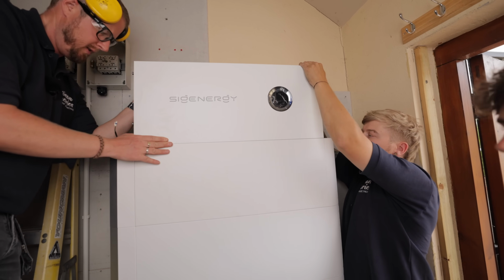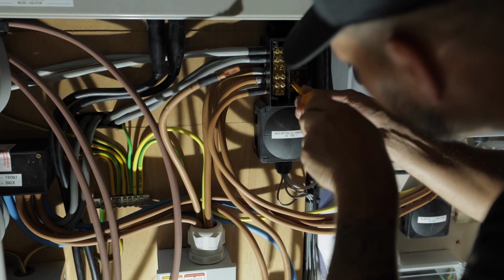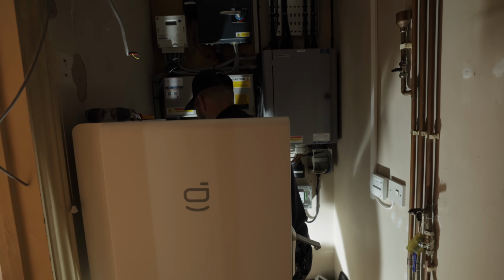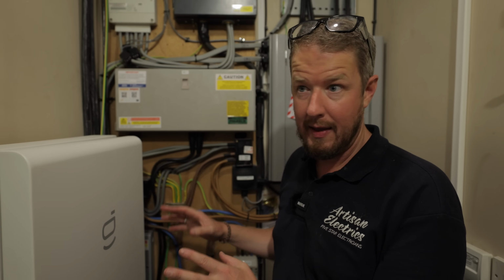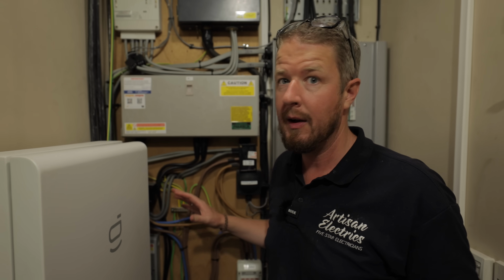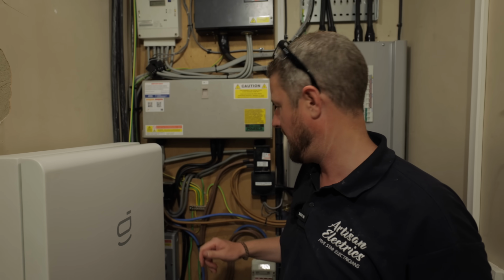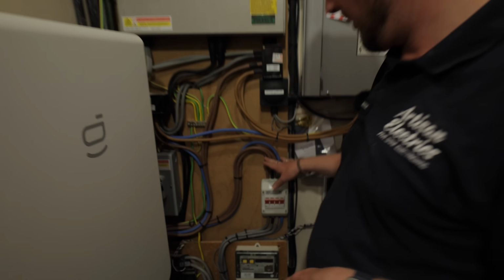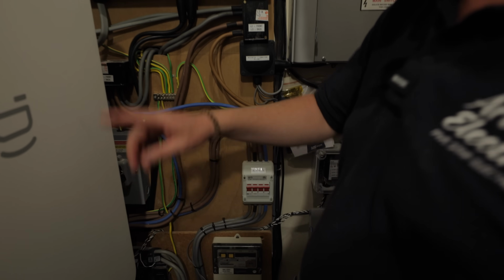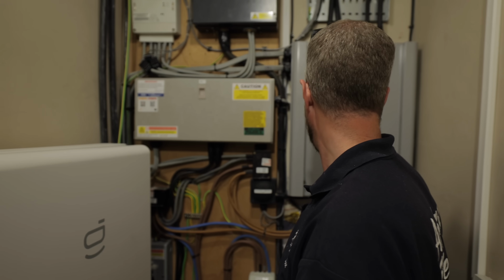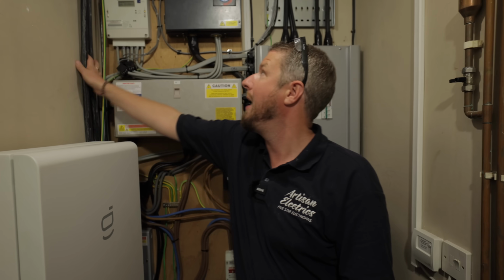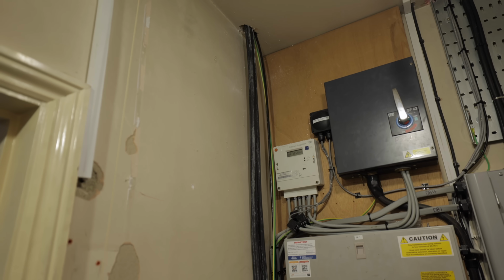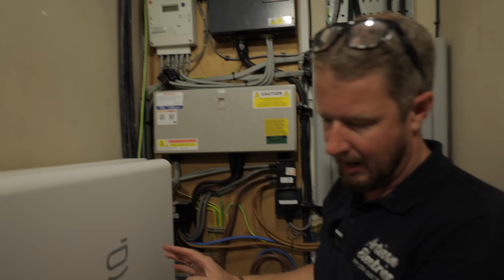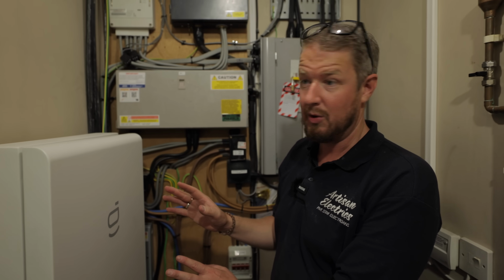Luke has done a great job getting the gateway wired in, and that's all on now, so we're running off the gateway. All the house power's back on, however, backup power's not going to work until the battery's connected. We've run our tails from the main isolator into the gateway, out of the gateway and back into these Henley blocks. We've got the cables down here, but we need to clip them all down and then terminate them into the gateway, which is a job for Reuben and Luke tomorrow.